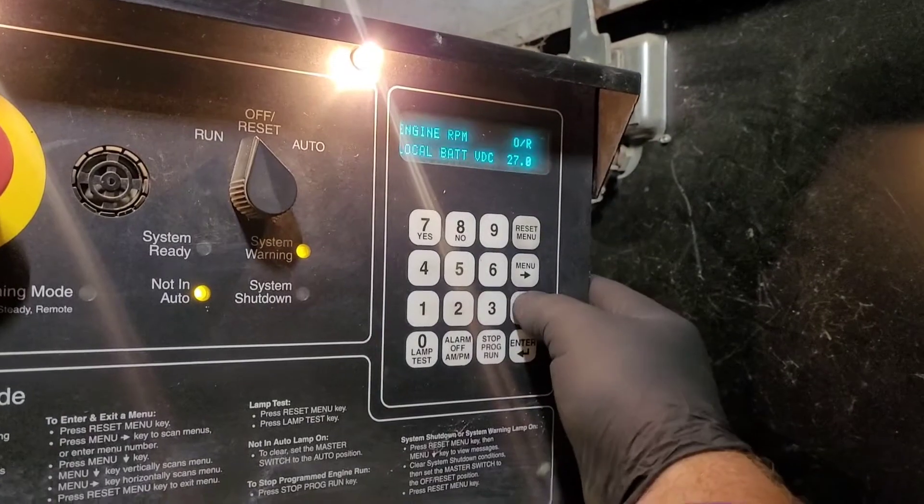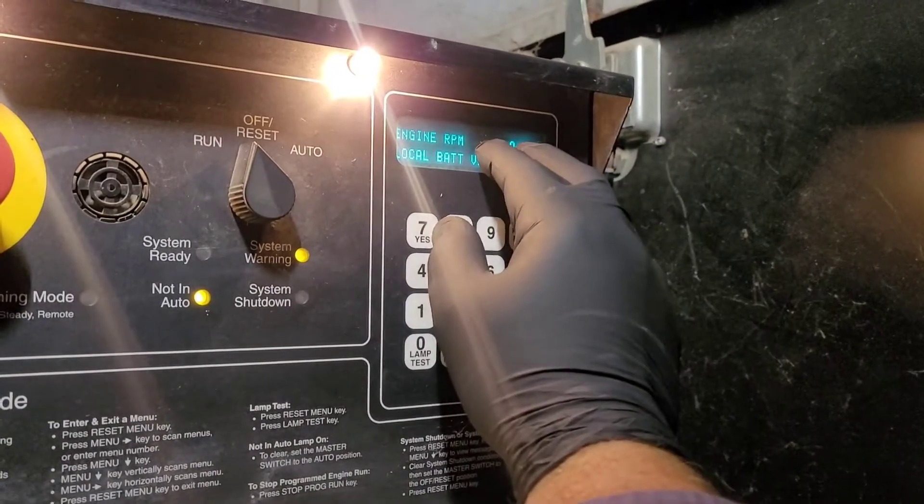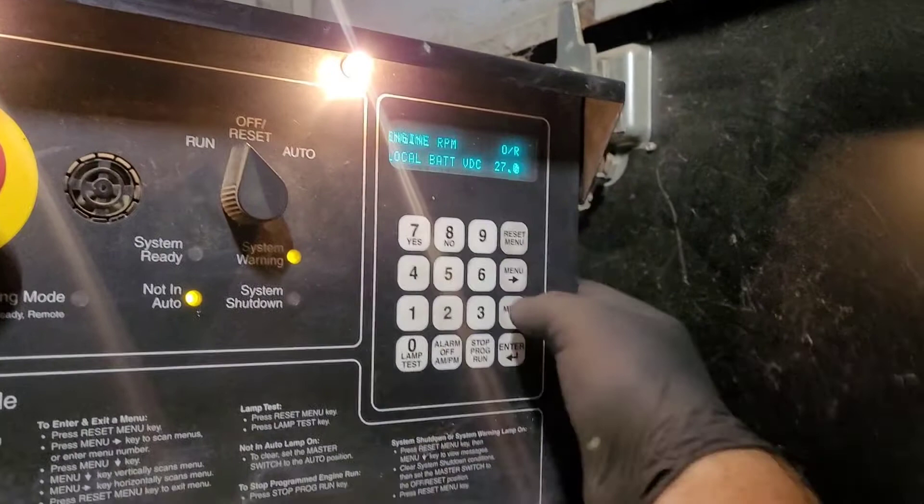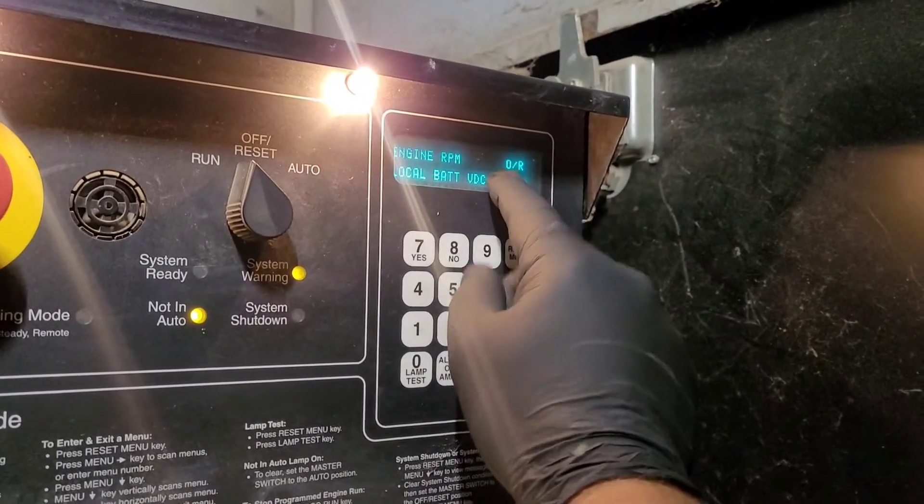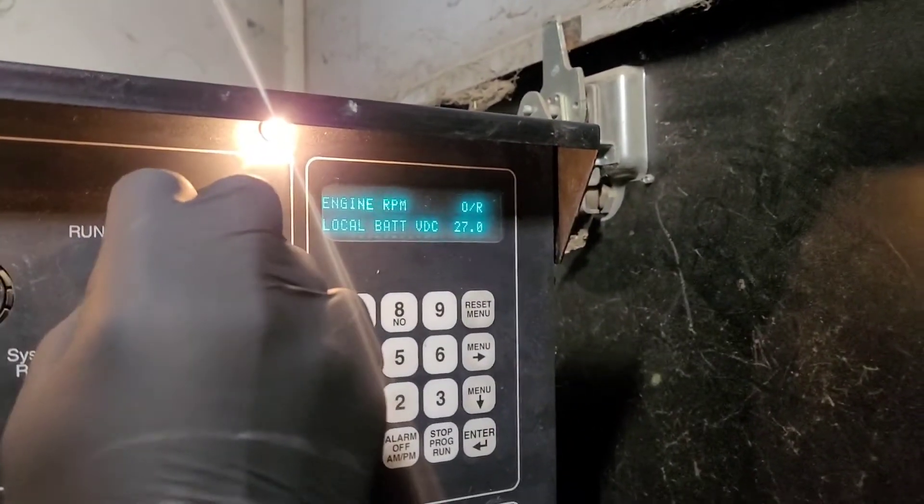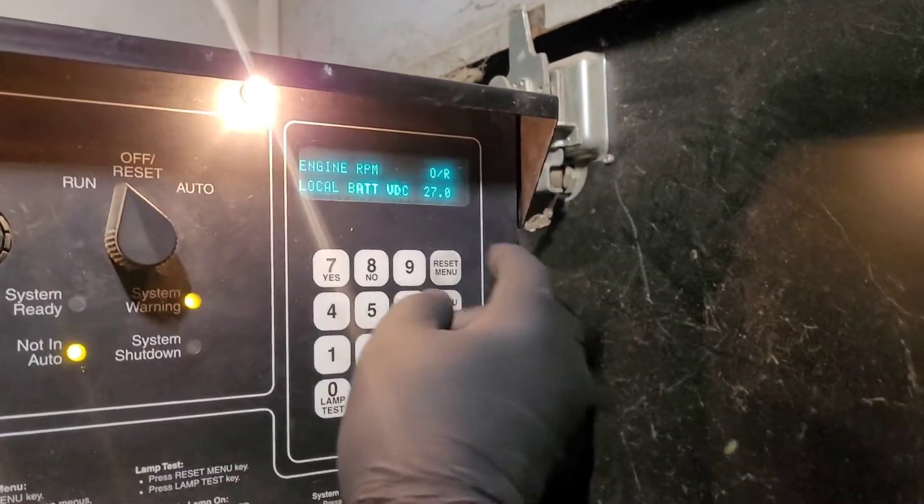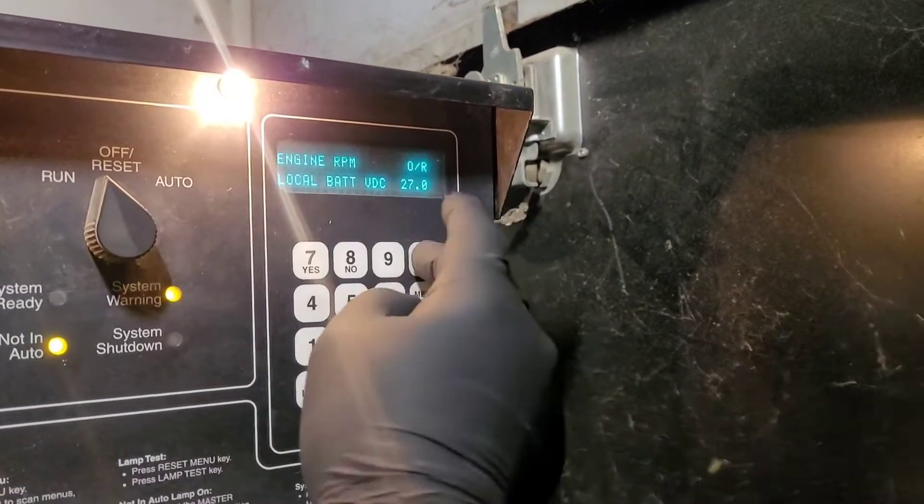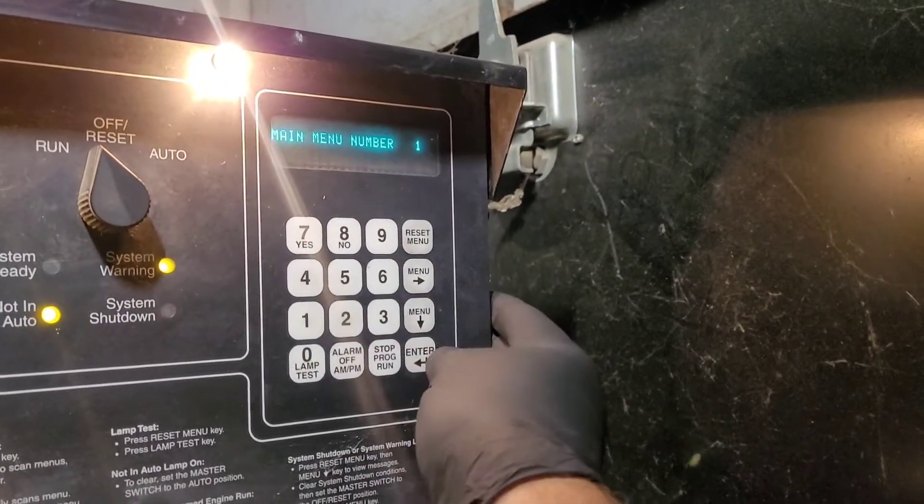Engine, see what the engine's doing, because once you hit it to run the menu won't change and I want to see what the engine RPM is when it comes up to speed. See if it actually comes up to speed. Actually first, because I don't think it's an under frequency issue, I think it's an undervoltage.